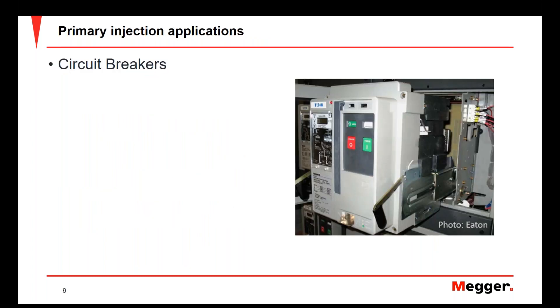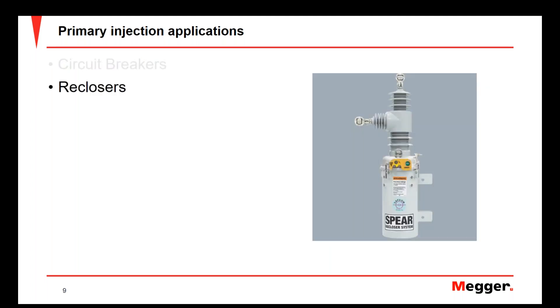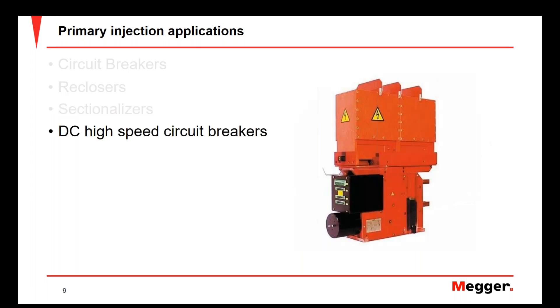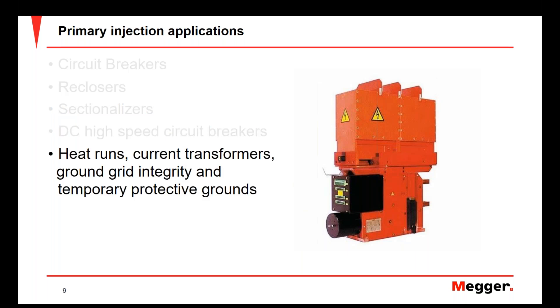Whenever we do this type of test, we drive current through a closed circuit breaker through the main contacts and verify that the overcurrent function is going to react as intended — tripping whenever we push current through the breaker. Primary injection applies to circuit breakers, but also to reclosers, sectionalizers that have overcurrent functions, DC high-speed circuit breakers, as well as heat runs, testing current transformers, verifying the integrity of ground grids, and testing temporary protective grounds.